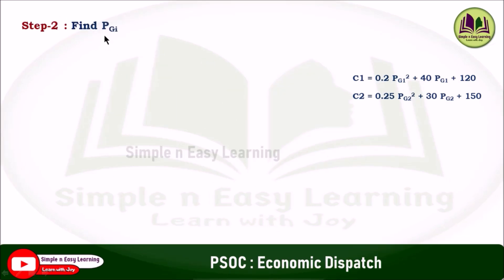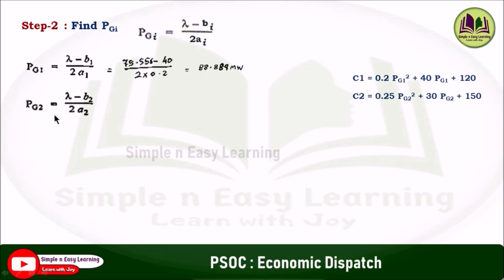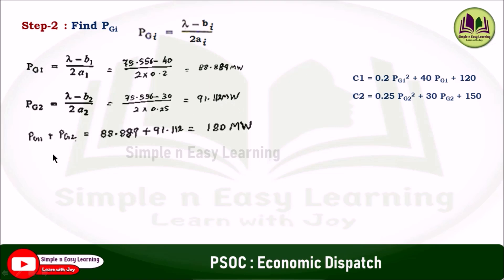Step 2: find the generation PGi using the formula lambda minus Bi by 2Ai. For the first unit, PG1 is equal to lambda minus B1 by 2A1. Substituting A1, B1, and lambda: 75.556 minus 40 divided by 2 into 0.2, that gives 88.889 megawatt. Similarly, for the second unit substituting the values of B2, A2, and lambda, we get 91.112 megawatt. Adding both generations gives 180 megawatt.